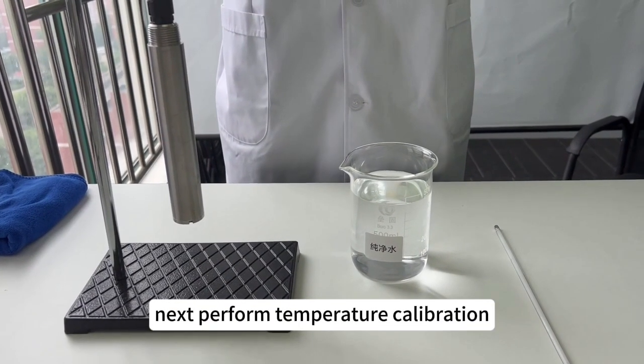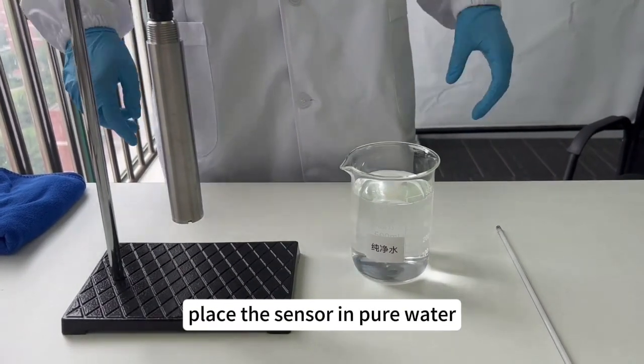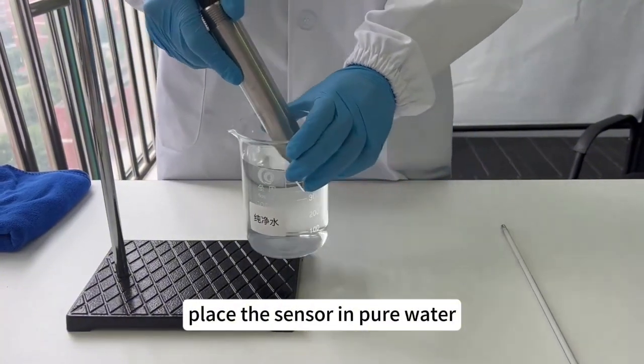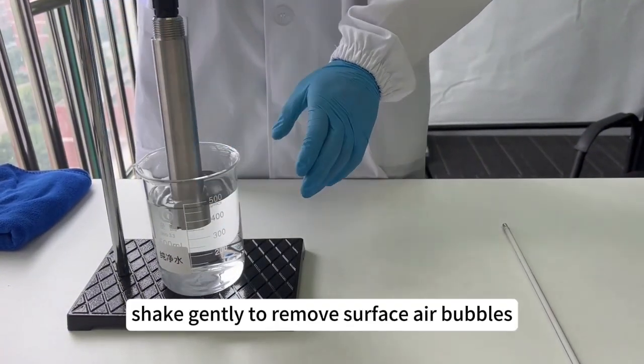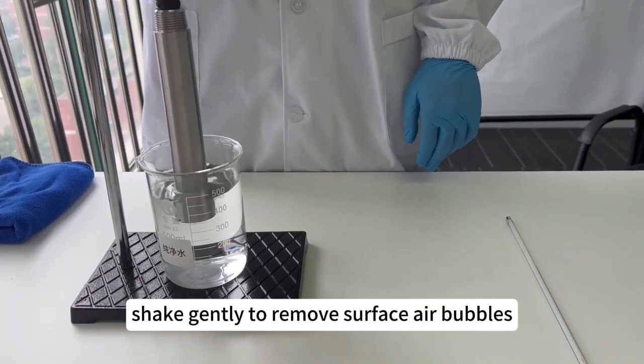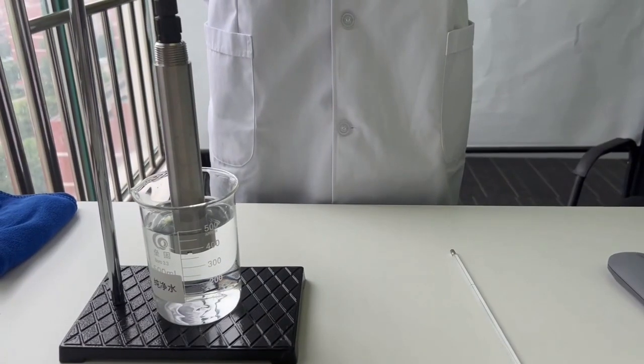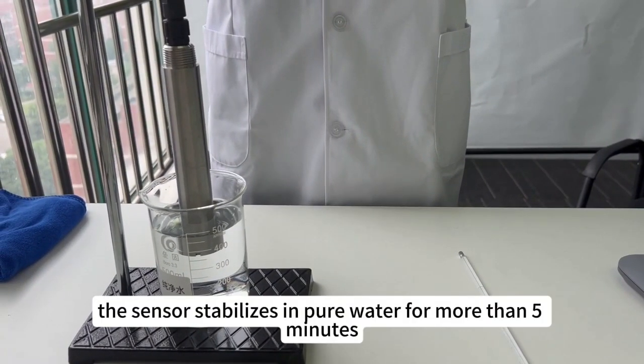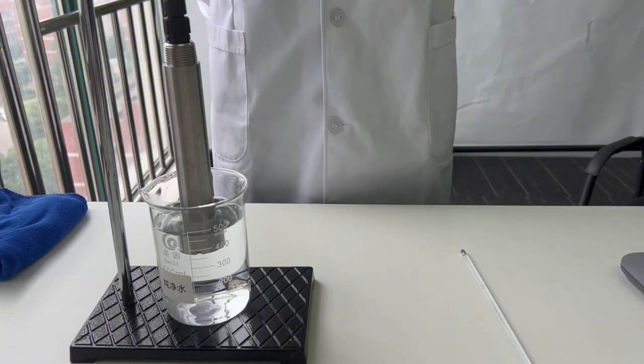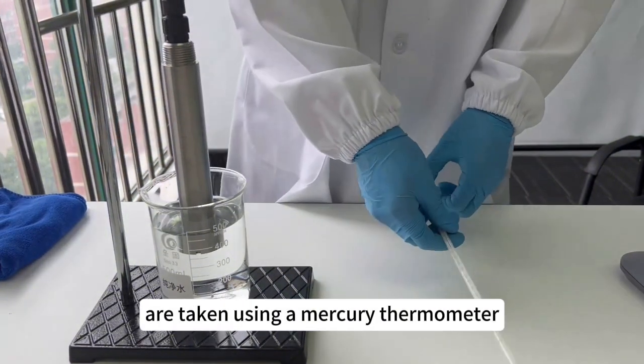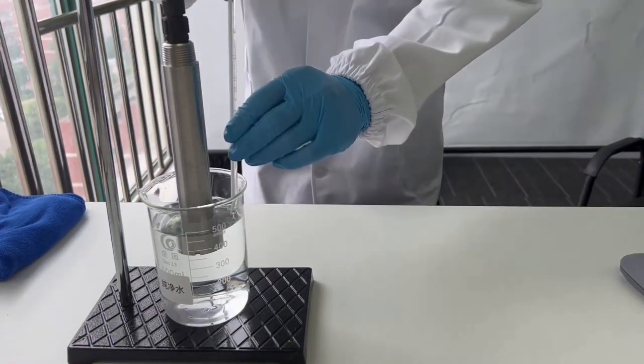Next, perform temperature calibration. Place the sensor in pure water. Shake gently to remove surface air bubbles. The sensor stabilizes in pure water for more than 5 minutes. Actual temperature readings are taken using a mercury thermometer.